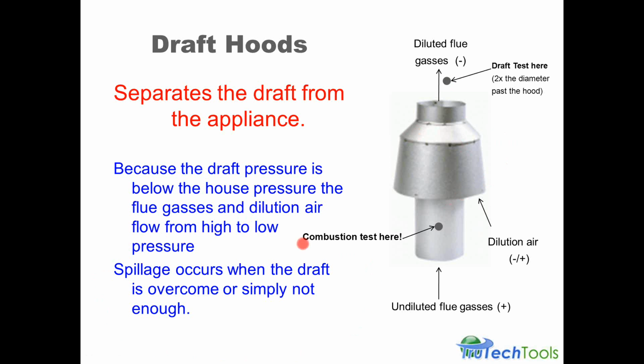I wanted to mention that spillage occurs when the draft is not strong enough, or it's overcome by a negative pressure in the room that pulls against the draft, or it's not strong enough to pull the undiluted products of combustion up the stack.